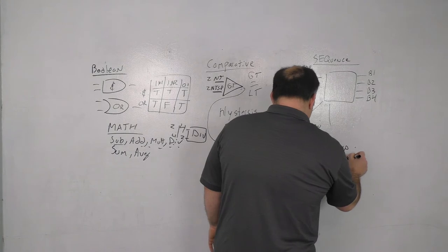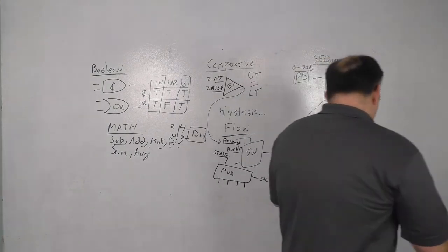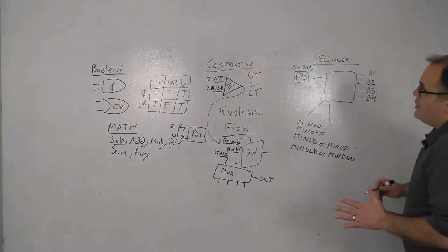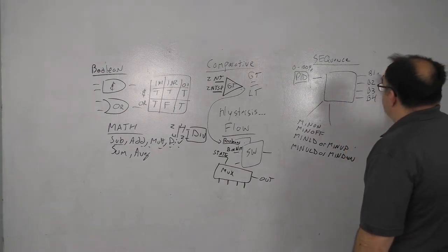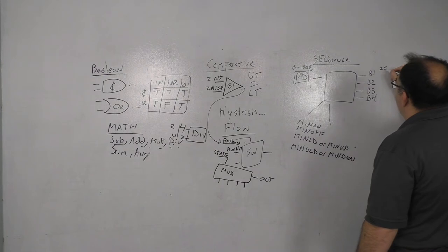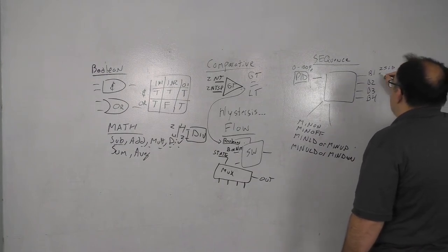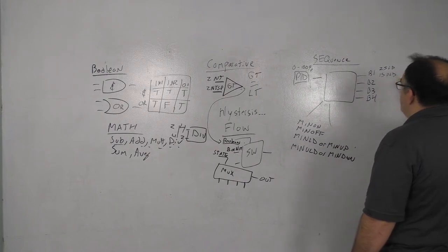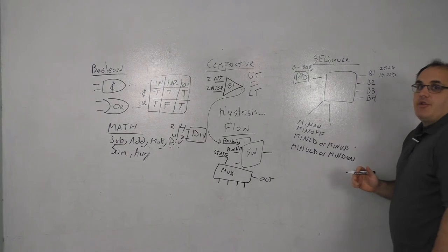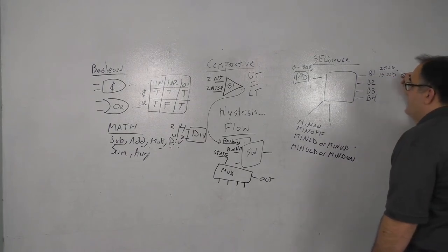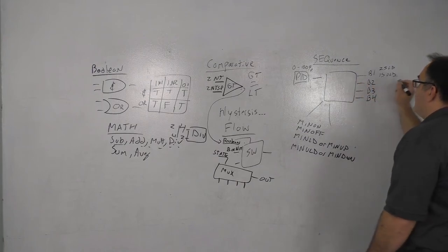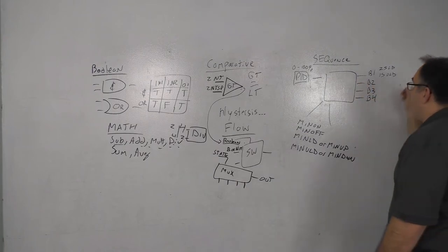Now, what is the difference? Here you go. So, I get this PID loop, and I have a min for this stage of 25 for my load, and let's say it's 15 for my unload. So at 25% or greater, I am going to turn on the stage. If the PID input drops below 15, I'm going to unload the stage. I'm going to turn it off.